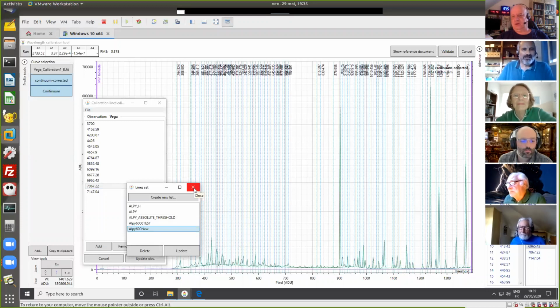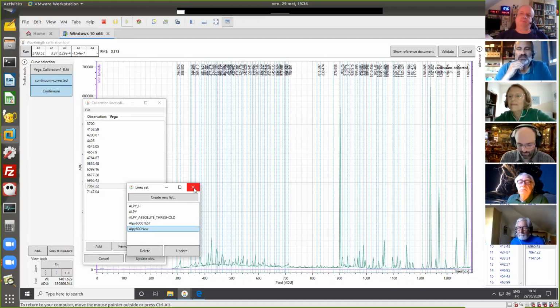So in the normal case, if you are using an Alpy with the standard calibration module, with the argon and neon lamp and so on, it should work. Really, it should work. If it doesn't work, maybe it is because your spectrum is not focused enough or something like that, but it is very highly probable that you can do it. Now, if you want to do that with another instrument, another spectroscope, or if you have any specificity in your system, or if you want to better focus on some part of your spectrum, you can edit this list and do what you want with it.